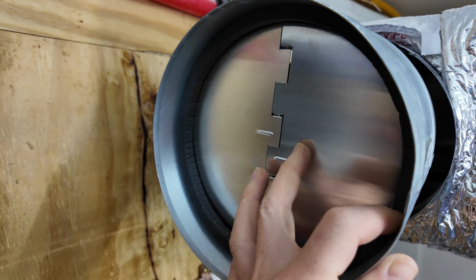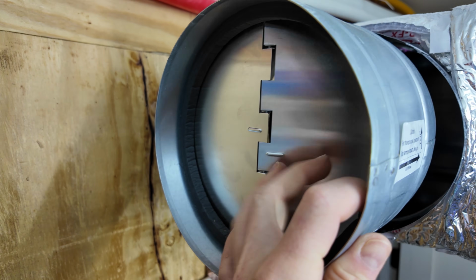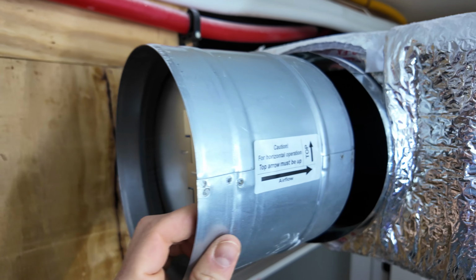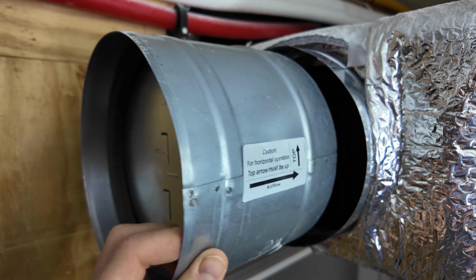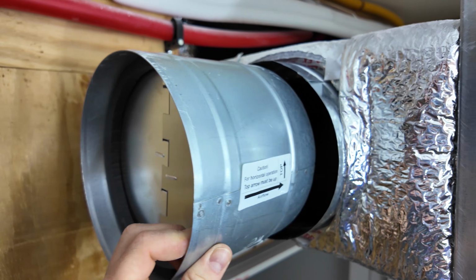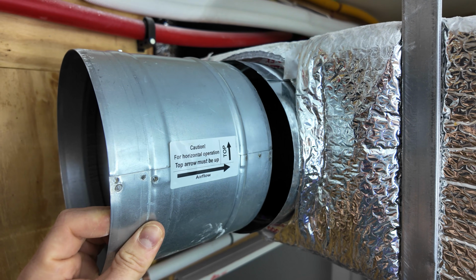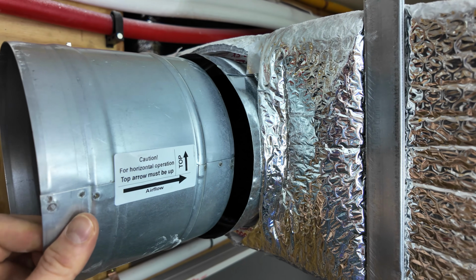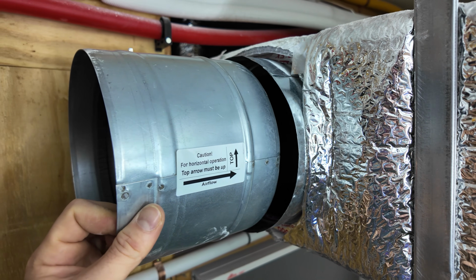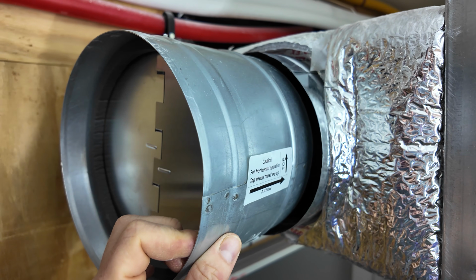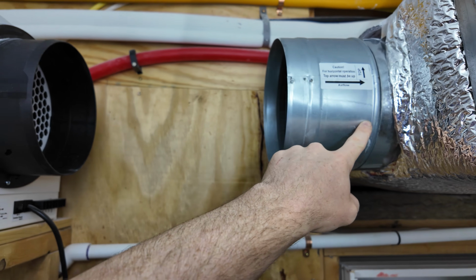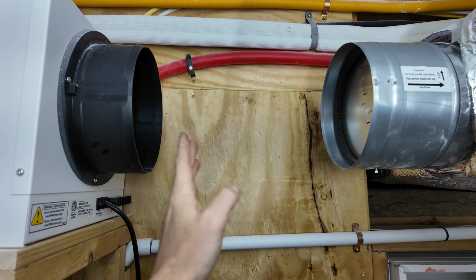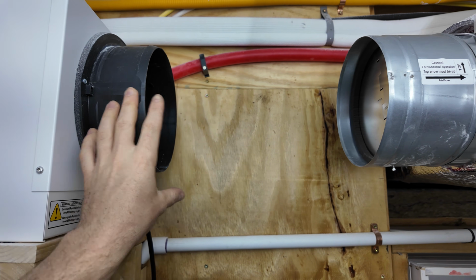The idea behind this backdraft damper is it's got this little butterfly valve on it. Air can only move that direction, in the direction of that arrow. That way, when the dehumidifier is not running and the supply trunk is pressurized from the main air handler, we're not pushing air backwards through the dehumidifier and up through that dehum return. It all goes to the supply branches. So I'll get this screwed and taped on there, and then we just have to bridge this little 1-foot gap here with a piece of 8-inch flex.